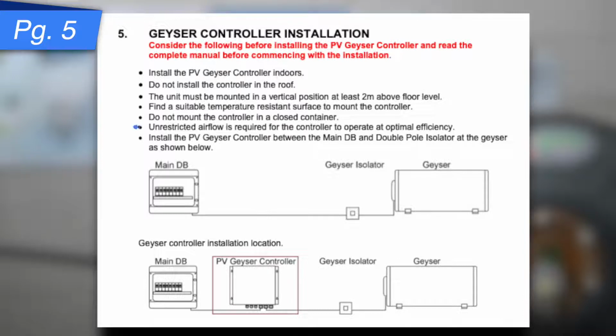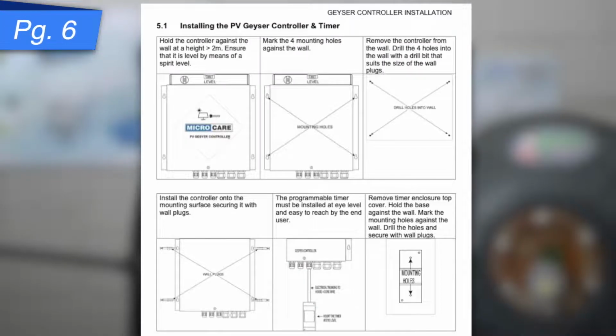So the next point, unrestricted airflow is required for the controller to operate at optimal efficiency. And then you install it between the main DB and the double pole isolator that's currently at your geyser right now. And you'll see that in the diagram on the bottom of page 5. On to page 6, it's installing the PV geyser controller and the timer if you choose that route. I won't go through that, it's fairly simple. It's just giving you indications of making sure it's level and how to find the correct drill holes.